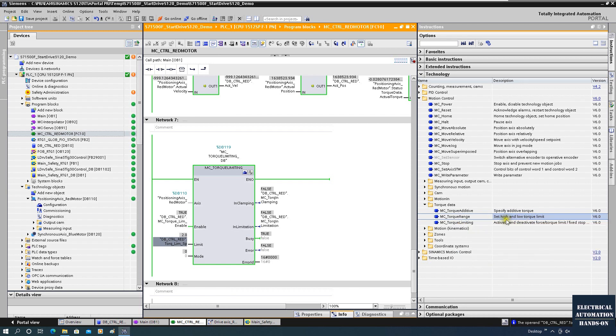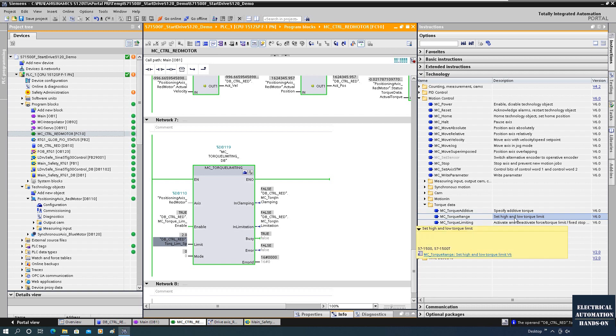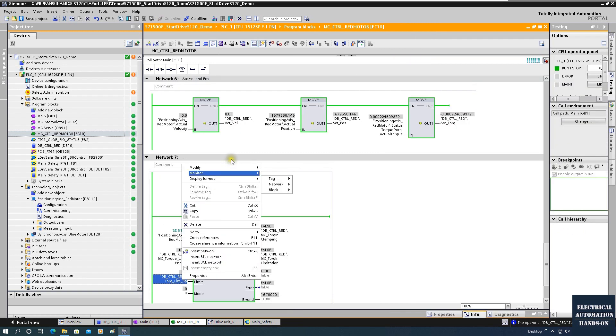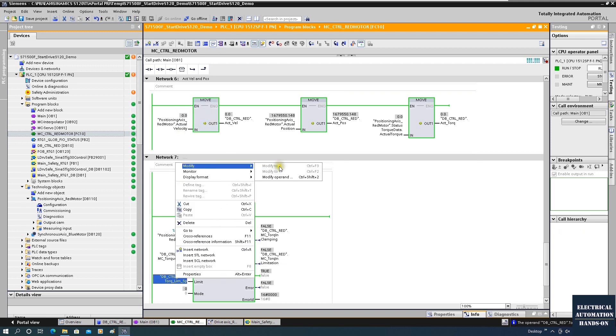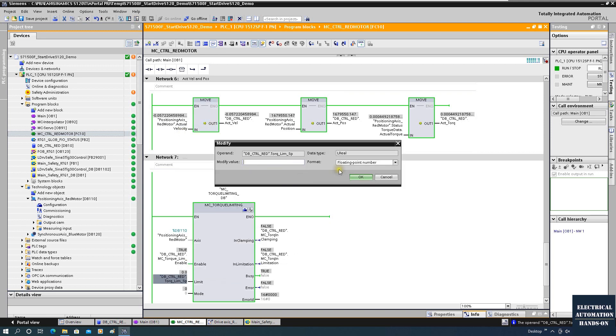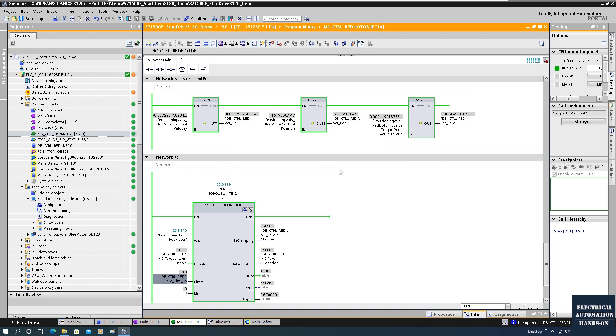In case you need to set the upper limit and lower limit separately with different values, you can go to the library and use MC_TorqueRange. From MC_TorqueRange you can set the high and low limits independently. That's the torque limiting — you can use MC_TorqueRange or MC_TorqueLimiting to limit the torque delivered from the motor.